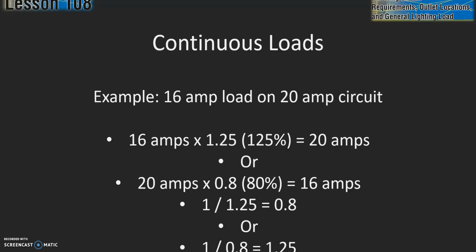But again, when you see those phrases, so you don't get tripped up, basically the circuit has to be a little bit larger or the load has to be a little bit smaller, but don't go vice versa. If the load is bigger than the circuit, we have a problem, and you've probably confused this formula here at some point.